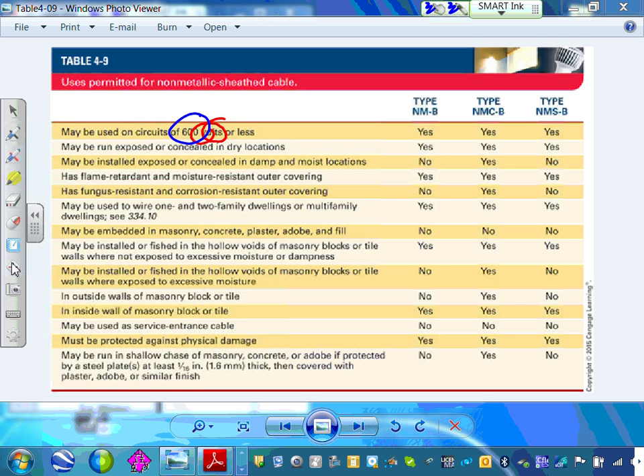So can you use it for 480? Yeah, it's limited to 600 volt. Can you use it for high voltage, 13.8 or 12.47? No. Can you use an MC cable for 13.8? Yes. You can see the difference between MC cable and NM cable. That's why a lot of engineers love the MC cable - you can get it in control cable, 24 volt, 600 volt, or 15,000 volt rating. This guy is limited to what? 600 volt.